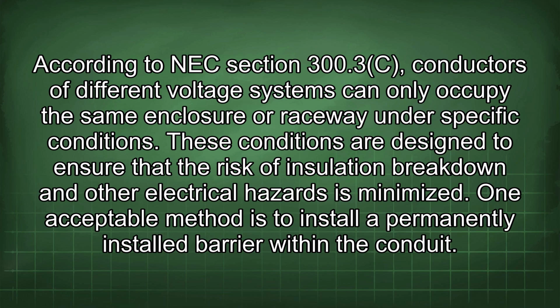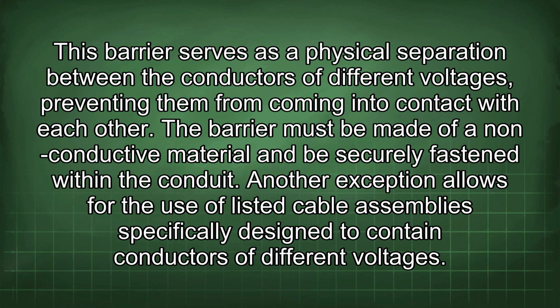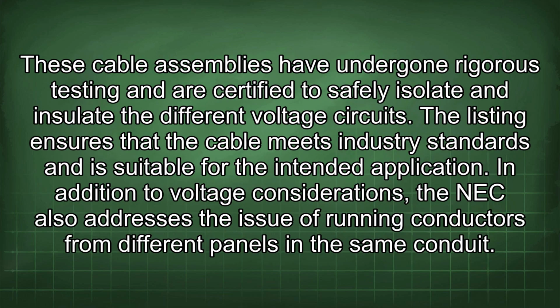One acceptable method is to install a permanently installed barrier within the conduit. This barrier serves as a physical separation between the conductors of different voltages, preventing them from coming into contact with each other. The barrier must be made of a non-conductive material and be securely fastened within the conduit. Another exception allows for the use of listed cable assemblies specifically designed to contain conductors of different voltages. These cable assemblies have undergone rigorous testing and are certified to safely isolate and insulate the different voltage circuits. The listing ensures that the cable meets industry standards and is suitable for the intended application.